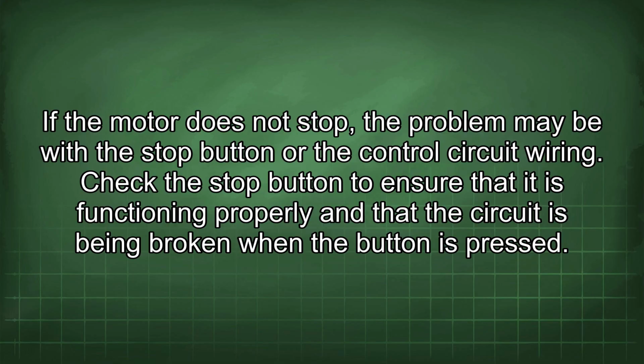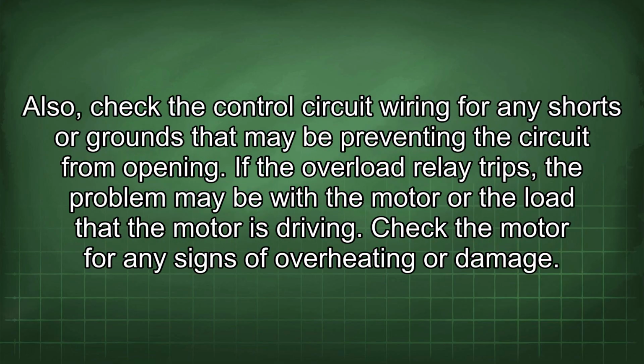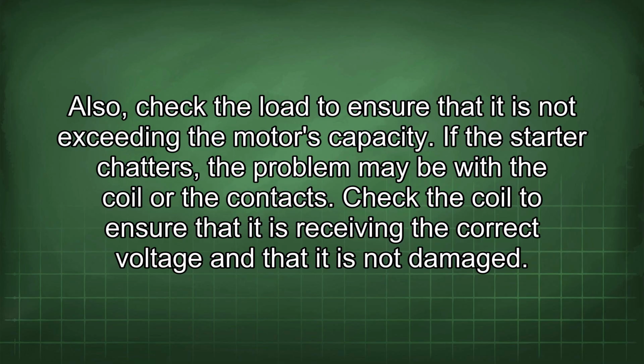If the motor does not stop, the problem may be with the stop button or the control circuit wiring. Check the stop button to ensure that it is functioning properly and that the circuit is being broken when the button is pressed. Also, check the control circuit wiring for any shorts or grounds that may be preventing the circuit from opening. If the overload relay trips, the problem may be with the motor or the load that the motor is driving. Check the motor for any signs of overheating or damage.